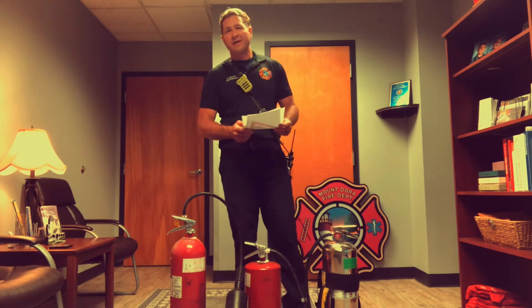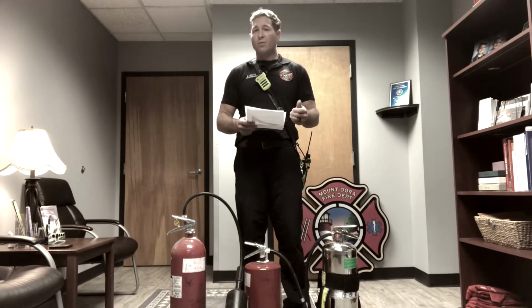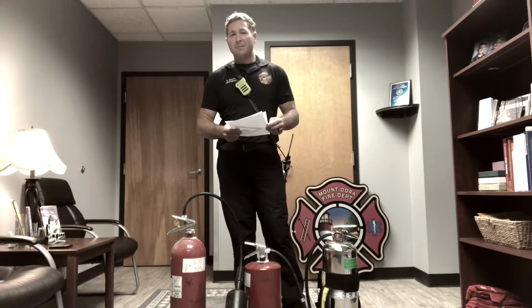Fires are classified by what is burning. Class A is combustible material: wood, paper, plastic, or anything of that sort. A Class B fire includes combustible liquids such as cooking oils and gasoline, just for example. C fires will have something to do with electricity. When something's on an energized electrical system, it'll be classified as a C. Class D fuels involve a combustible metal such as magnesium, and Class K fires are strictly dedicated towards cooking oils.